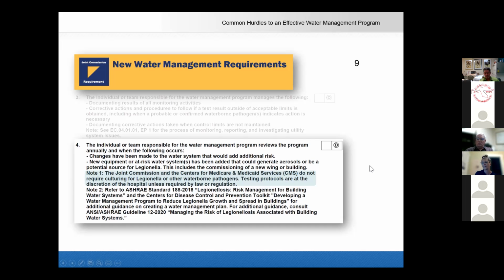But the second note refers to the ASHRAE standards, in particular the Legionellosis risk management for building water systems. So if you've decided as a facility that you're well covered and have great controls, and you're not sampling for Legionella or waterborne pathogens, you need to document it. Although it's a recommendation and not necessarily required, if someone audits you, you need to be prepared to explain, hopefully with evidence-based monitoring data from your water management team, why you chose not to collect samples or not to do something called out in this standard.